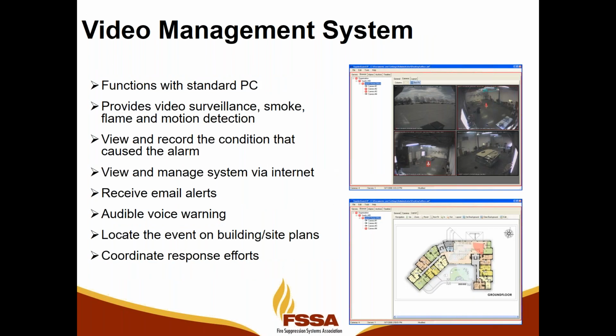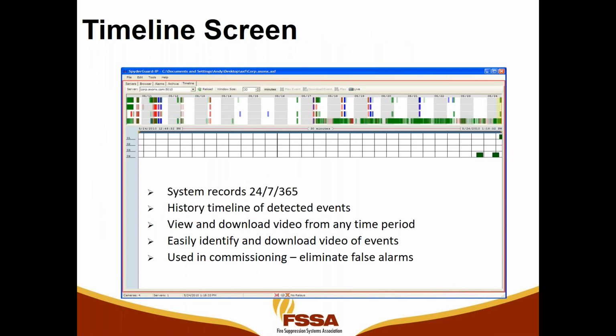So, video management software is available to view the camera video live. Also can put a plan view in the software so you can see where the detectors are located. A timeline is used to identify when events occur, and you can go into the timeline and download events. So smoke is blue, flame is red, green is motion. The system is recording 24/7, 365, first in, first out. With the new servers, they're about 12 to 18 terabytes, so you get about 45 days worth of recording.